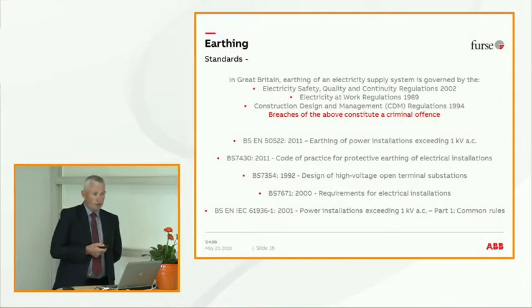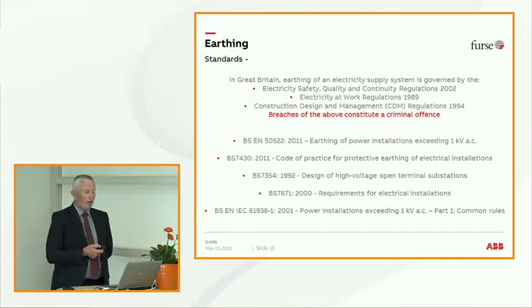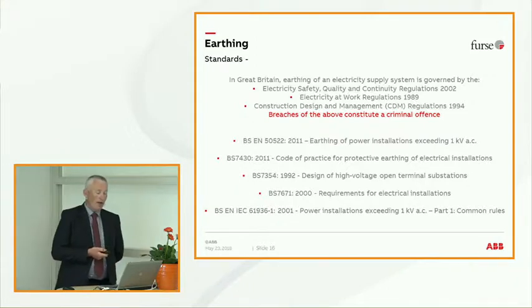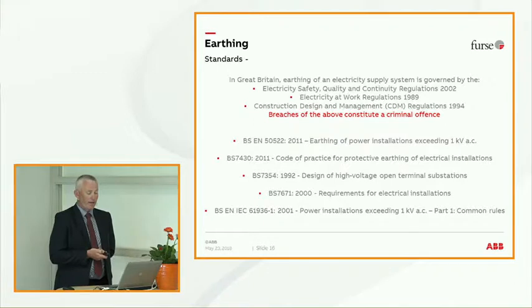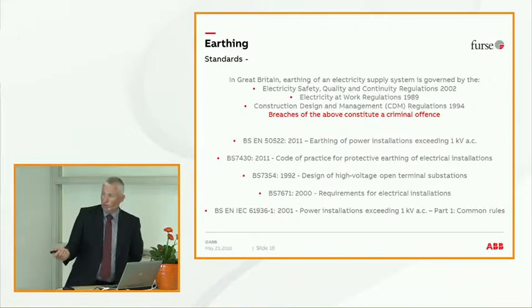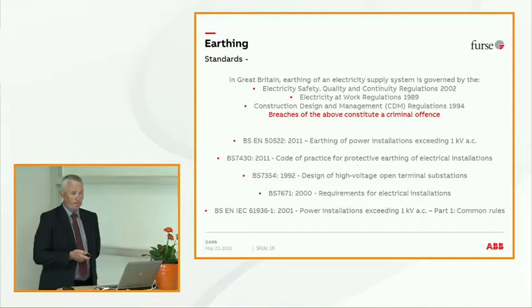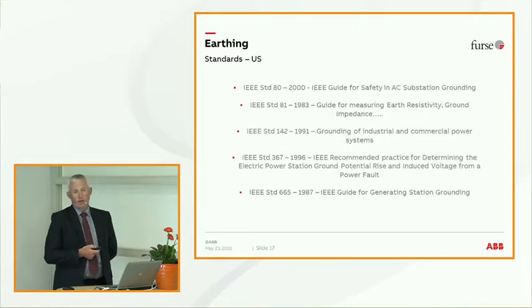There are several standards when it comes to earthing. Now, these are the BS standards I'm referencing here. These standards are recognised all over the globe. They're used in many countries around the world, and they've been adopted in certain aspects by the IEC. So it could be for electrical installations, substations, general power installations, and then you've got whether it's a power installation over 1 kV. I know we've only got the one reference to IEC here, but all these are used all over the world. Other standards that are recognised globally are the American standards.